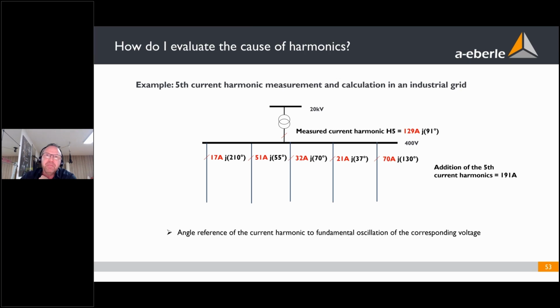It's much more useful. This is a real measurement at the industry customer. We measure each cable, we measure the 5th harmonic. And if you add the 5th harmonic of all these different machines, we have a current of 190 amps. But if you measure the 5th harmonic at the transformer, you will recognize that the sum of the current is much smaller.